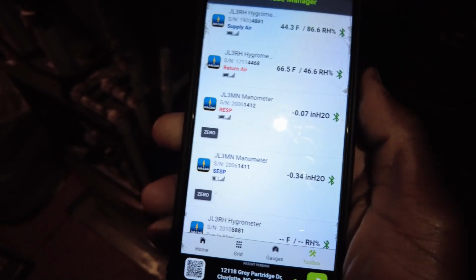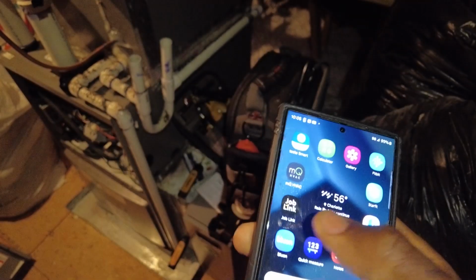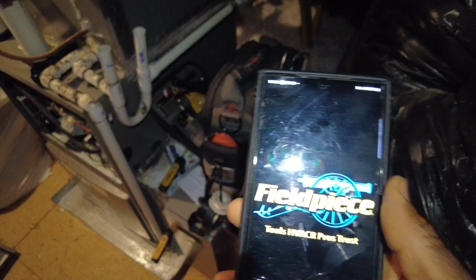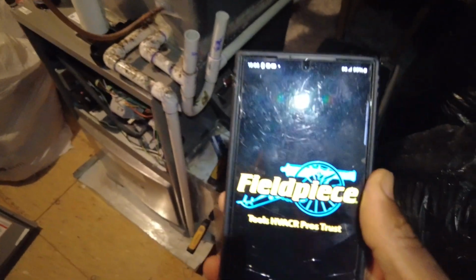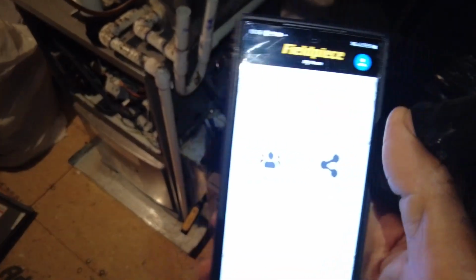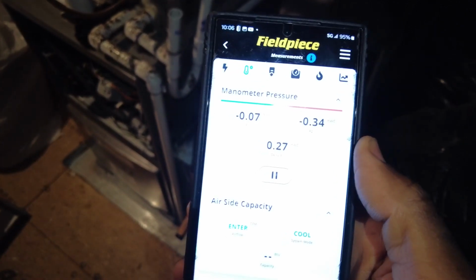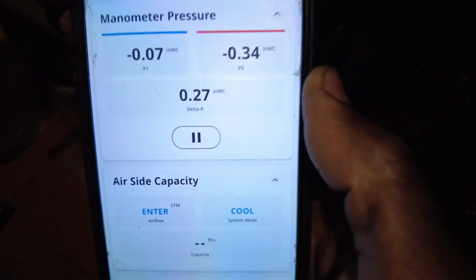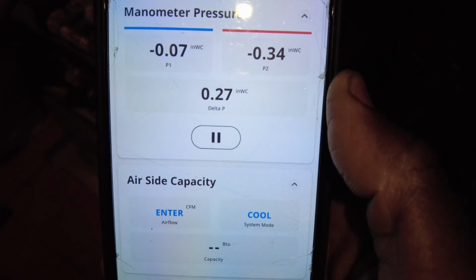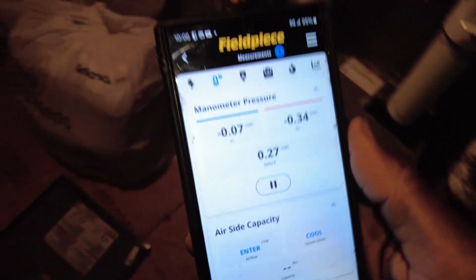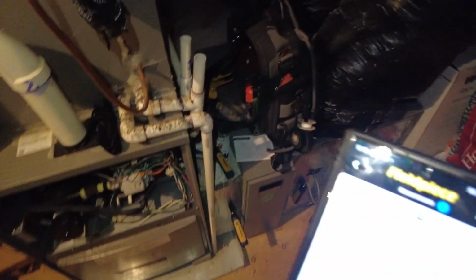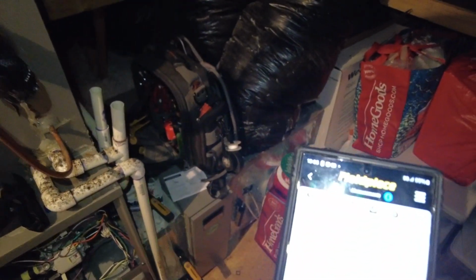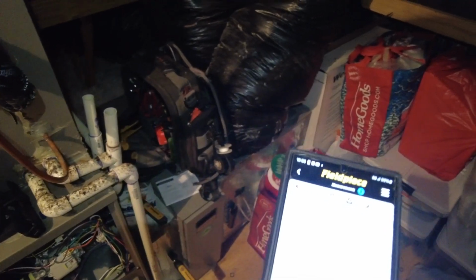So that's going to help out a lot. 0.34. Let's take a look at the job link. It shows a much better, it'll show your actual drop, your differential, without having to do the math. So your 0.27 drop, which is not terrible. It's not the end of the world, but if we can get that down to like a 0.15 or something, I think that'll help.